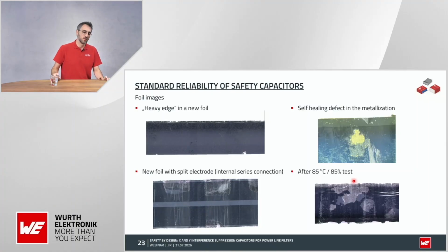This is also similar to the graphic I showed you. Here you can see corrosion and partial discharge degradation on the edge and also in the middle of the foil. This is a different foil after the 85/85 test.